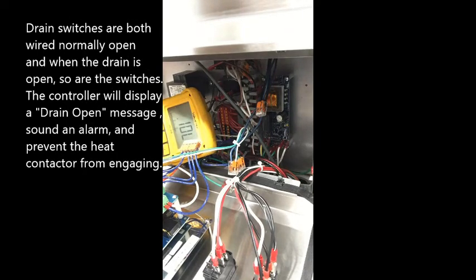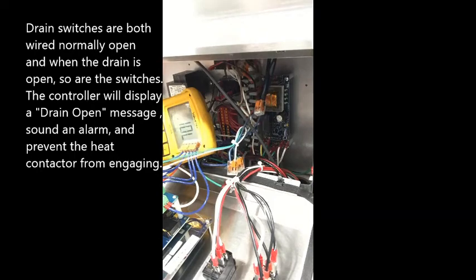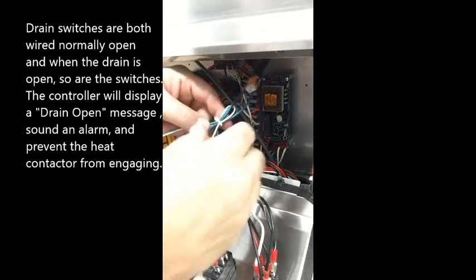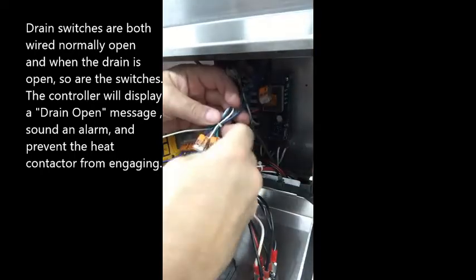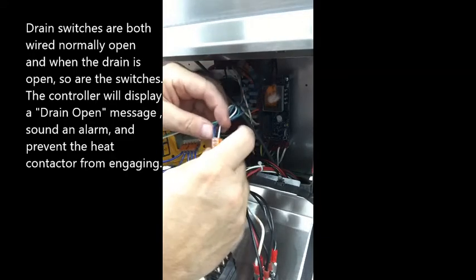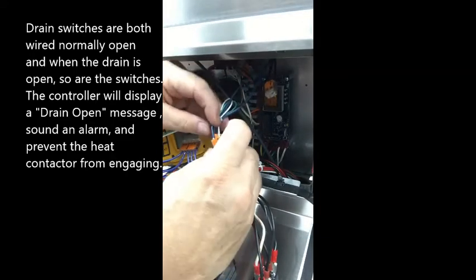Okay, so let's say that you're getting a drain switch error, and you've determined that when you close the drain, both of the plungers are up, but you want to get the customer running while you're waiting to get the replacement drain switch. More than likely, it's just one of them that's gone. So if you follow this green and this white wire up, what you'll find is that they go right here and they terminate at these blue wires.